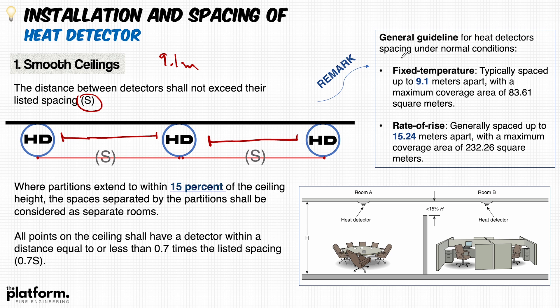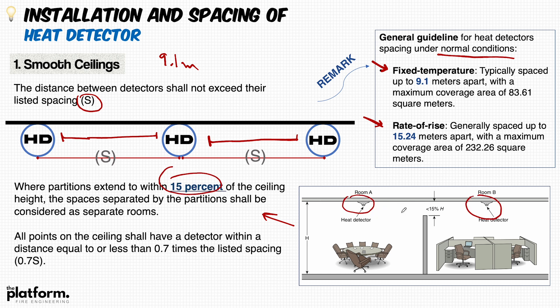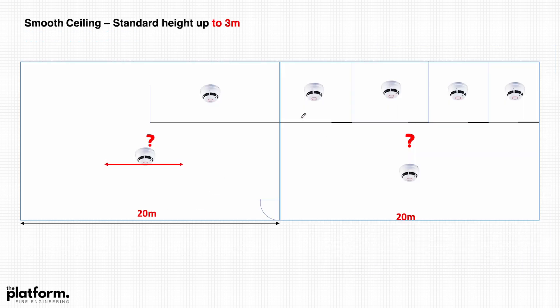The general guideline for heat detector spacing under normal conditions with a smooth ceiling — referred to by NFPA 72 — applies to both fixed temperature and rate of rise types. For partitions, the same rule as smoke detectors applies from previous lectures: the 15% rule for determining whether to provide a heat detector in each partition or treat the area as one space. The standard maximum installation height for heat detectors is 3 meters.